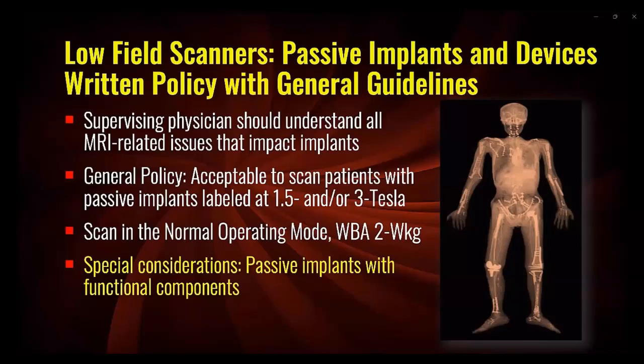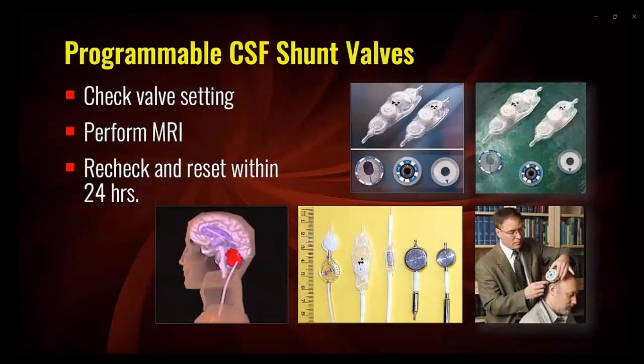Special consideration should be given to certain passive implants with functional components, such as programmable cerebral spinal fluid shunt valves, magnetically activated orthopedic implants, or similar devices. For a programmable CSF shunt valve, follow labeling conditions indicating that a suitable healthcare professional should check the pressure setting of the valve before the MRI exam, then recheck and reset it as needed afterward.